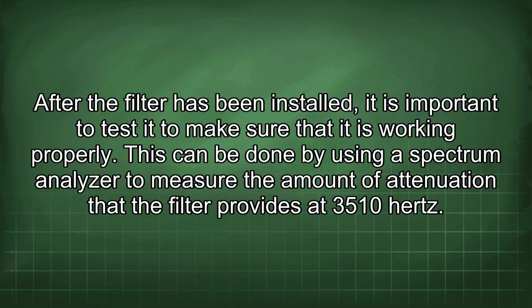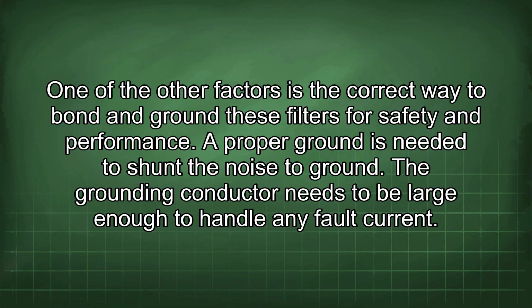One of the other factors is the correct way to bond and ground these filters for safety and performance. A proper ground is needed to shunt the noise to ground. The grounding conductor needs to be large enough to handle any fault current.